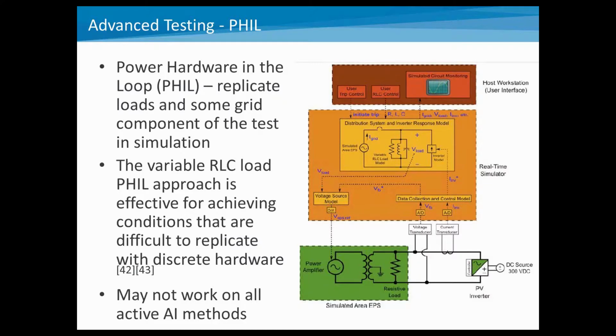And one of the things that we did was some advanced testing looking at could we replicate the load bank and grid conditions in what we call hardware in the loop or power hardware in the loop. And what this allows us to do is not use a physical load bank, but actually simulate the load bank conditions. So there's some references on this particular type of testing, but we were able to basically replicate and validate the tests that we typically do in full hardware with the ability to replicate that in software. And it also actually allowed us to much more finely tune these resonant tank circuits.